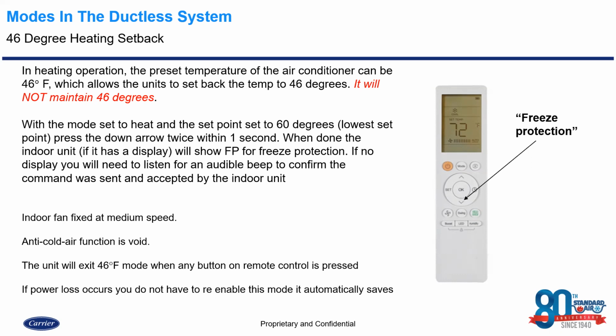Okay. One thing to note about the 46-degree heating setback function on here that's very misleading is that when this is put into place and the unit is set back to allow the temperature to fall to 46 degrees, when this goes below 46 degrees, we'll just say it went to 44 degrees, the system kicks on and starts to run heat. It does not maintain 46 degrees. What it does do is go to the lowest set point that we have for these systems, which on this newer style is 60 degrees. So what does that mean? Well, indoor temp fell to 44, heat kicks on. It's going to warm the space up to 60 degrees, satisfy at that 60 degrees, shut off, and then let the temperature fall back down to 46 degrees again.